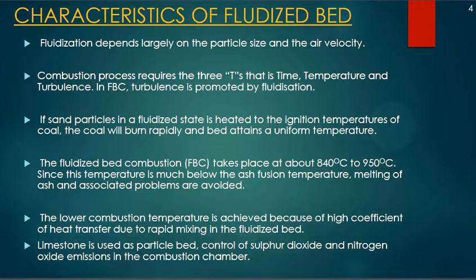In the combustion process, there are basically three things which are very important. One is the temperature, the second is the turbulence, and the third is the time. In fluidized bed combustion, the turbulence is the most important and the most advantageous thing.